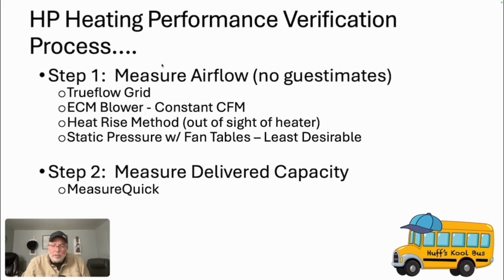Now, on this kind of test, I'll be honest with you, I'm going to be using the heat pump non-invasive check. The reason I'm doing that is because right now I'm just trying to determine the capacity of the system with the heat pump running without any help of aux heat. And I want to see what the delivered capacity is of the heat pump as it's running. Now, I'm not going to be checking pressures. I'm not checking the charge at this point. I'm trying to determine how the system is running at this moment in time.